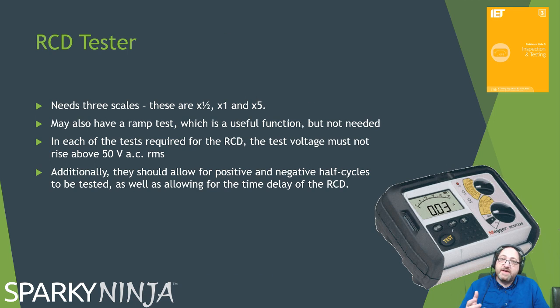We have the RCD tester. It must be able to test at times half, times 1, and times 5 for ADS purposes. Some RCD testers have a ramp function, which isn't a requirement, but it's quite a useful diagnostic tool for nuisance tripping. It's important with this test to verify the earth fault loop impedance first, as the RCD test must not rise above 50 volts AC RMS at any time, which is why the test is only carried out for a fraction of a second, because we can't allow dangerous voltages to build up if there's ineffective earthing in the area.